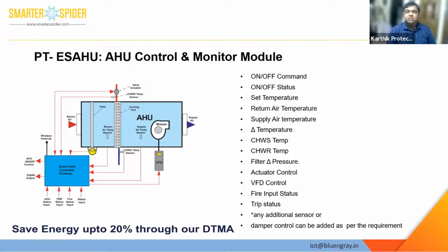We have seen cases in one of the hospitals where, because of non-timely cleaning or non-proper maintenance, due to clogging, there was an issue of infection. So once we have deployed our system, because we have an alert system, it will regularly alert the maintenance team if it's crossing the set point, so they take care of the filter cleaning. So you have a clean flow of air passing through the duct.